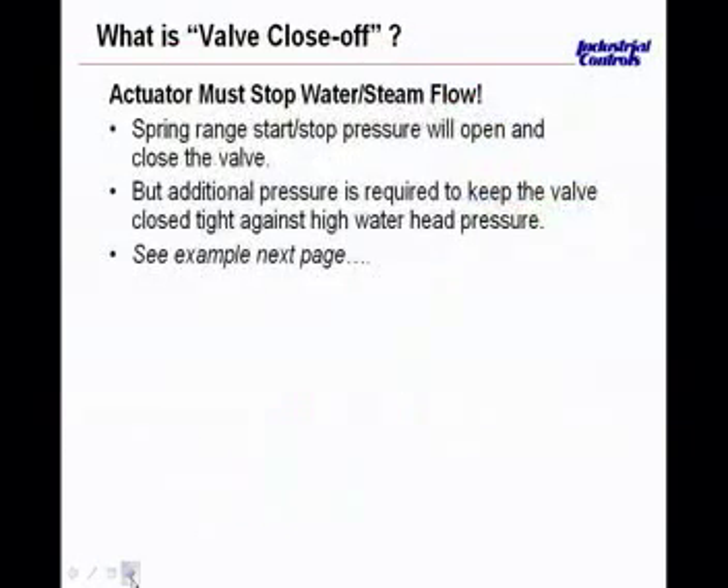Close-off rating, or valve close-off: a valve must be able to stop the flow of water or steam when controlled and told to do so. A valve and actuator combination can be selected to close off tightly against normally operating conditions, but can leak if the water or steam pressure increases. Pumps may increase pressure at times, and water is not compressible, so head pressure can easily exceed a valve's close-off rating and push the disc or plug off the seat, opening the valve and letting steam or water flow through. Even small amounts of leakage will cause loss of control, wasted energy, premature valve wear, and can cause the entire system to fail.